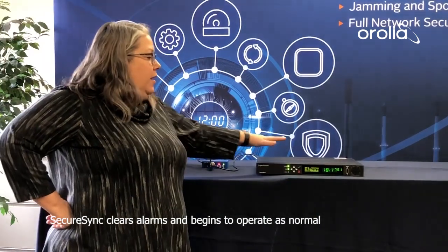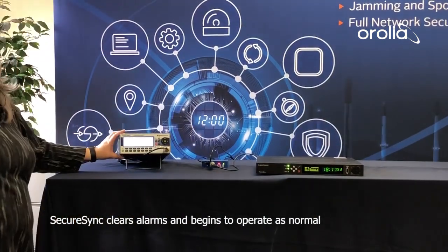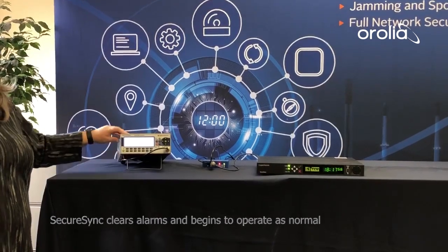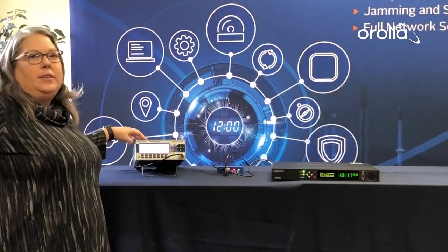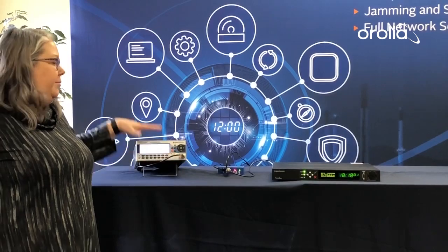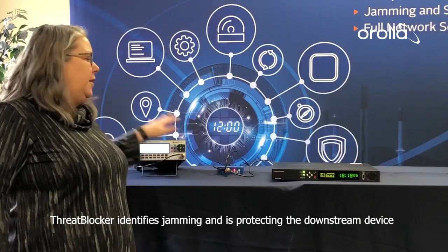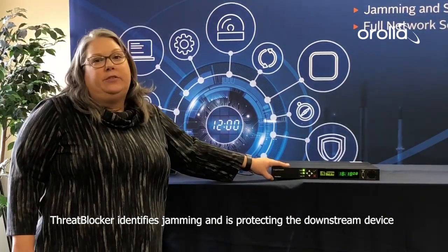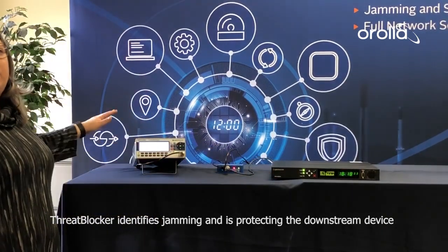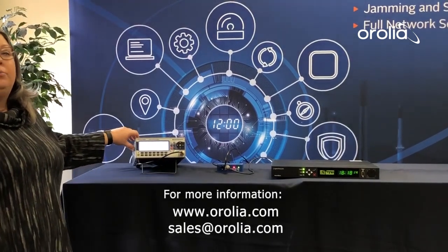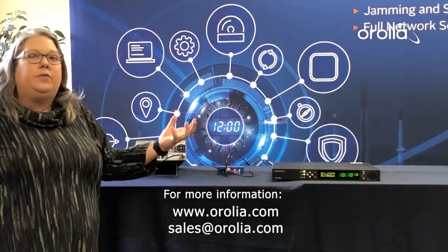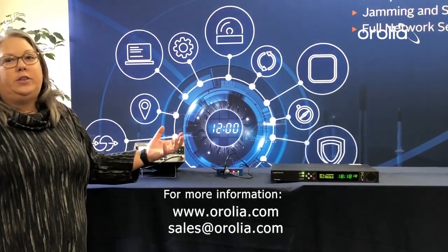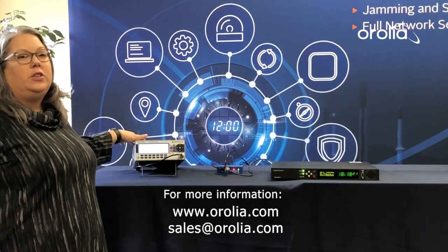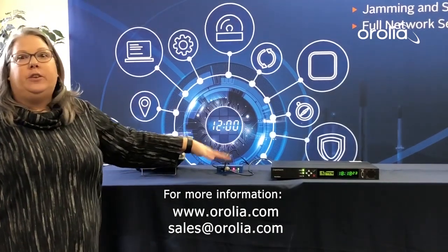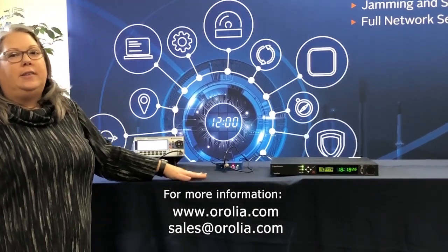And there we go. So now, even though the jamming signal is still present, I didn't remove it. It's still just as strong as ever, and I'm using a very strong jamming signal for this demonstration to make sure that everything gets fully jammed. ThreatBlocker has identified jamming, that's why the jamming light is on, and is protecting the downstream device, which is the SecureSync. So even though we're still in the same environment, the jamming signal is still present, if we were here trying to use our cell phones for navigation or anything, they wouldn't work. GPS would be totally denied in the region of this jamming signal. SecureSync can continue to work because ThreatBlocker is in line and protecting it.